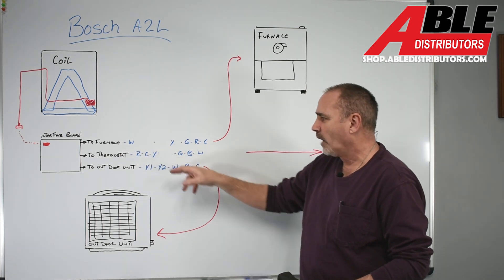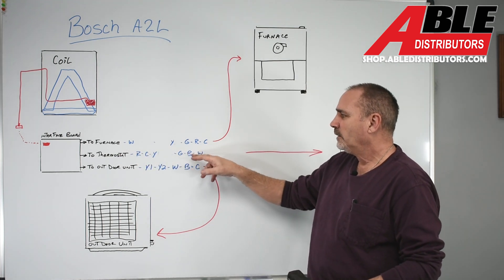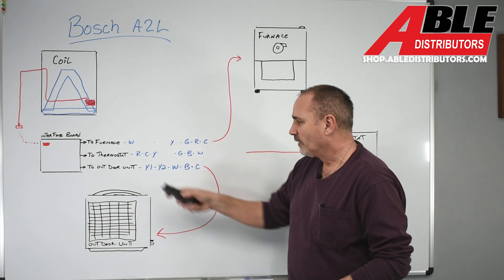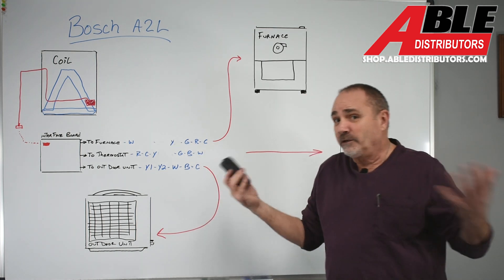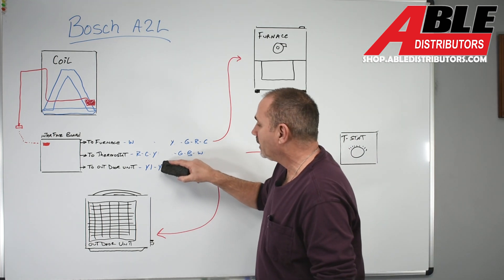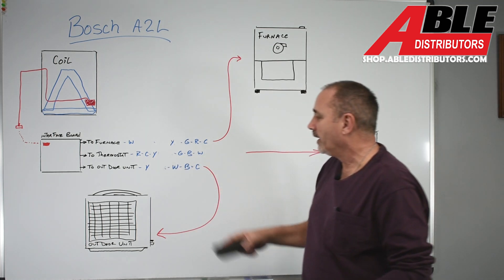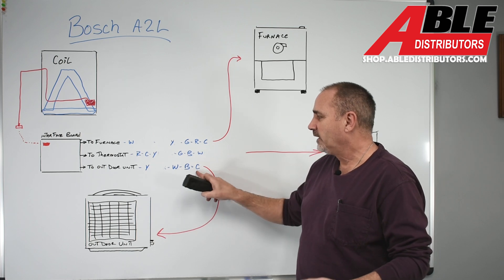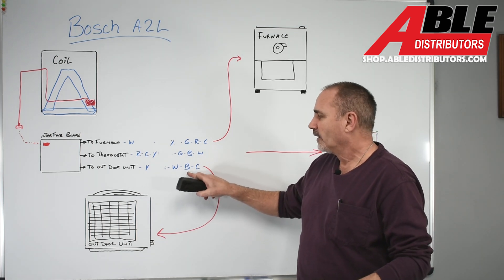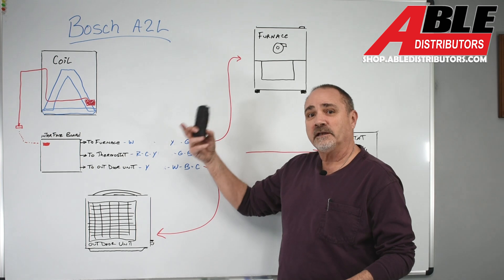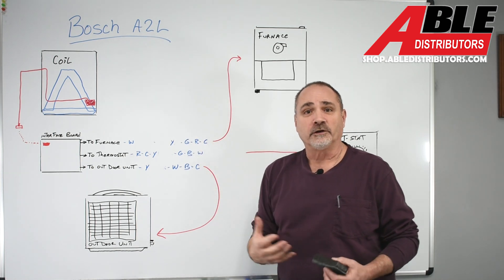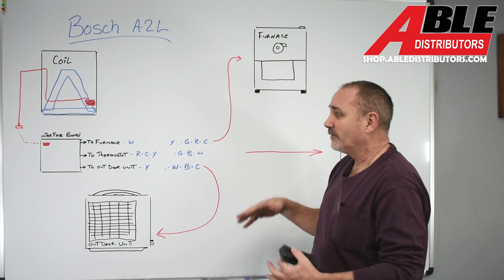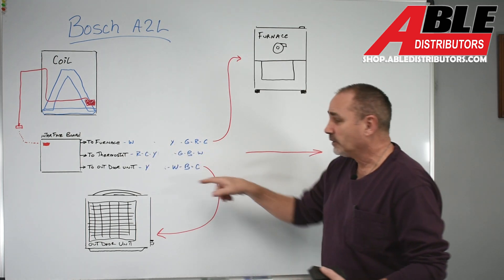To the thermostat, R, C, Y, G, your reversing valve, and your heat. And then to the outdoor unit, again, you're putting in a Bosch. You don't need, it's just going to be a Y. So you're going to want Y for your AC, C to power your AC, B for the reversing valve, and W to send the signal back to the furnace to turn on heat while you're in defrost. So if you're doing a standard basic install, that's all you need. Cap off all the other options.